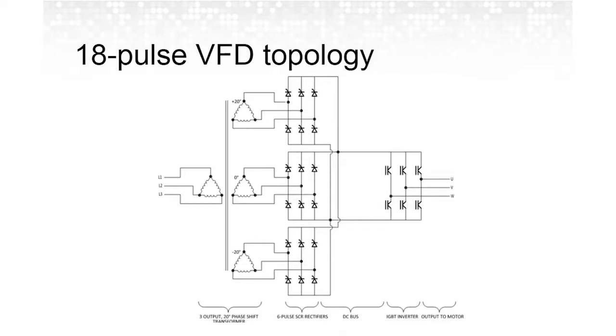If you go one step further beyond it, there is the concept of an 18-pulse VFD. So if a 12-pulse VFD is good for addressing harmonic distortion, the 18-pulse is even better. Instead of an input transformer that has 2 outputs, we have a 3-output transformer with a 20-degree phase shift. And that feeds 3 parallel 6-pulse rectifiers. And this draws power 18 times per each complete sine wave cycle for the 3-phase input.